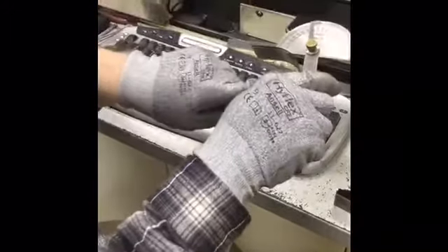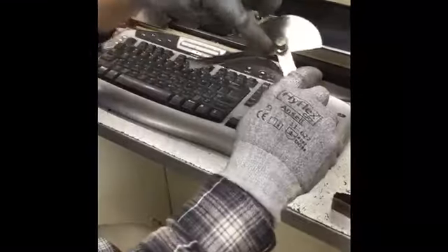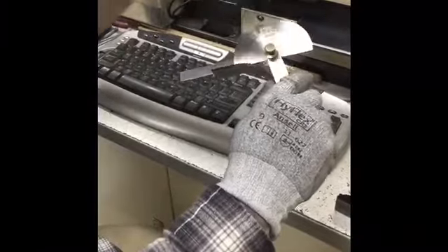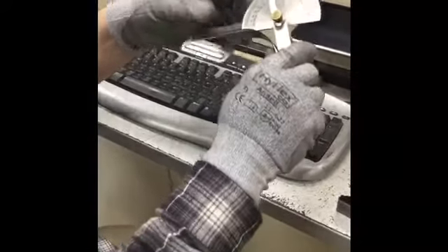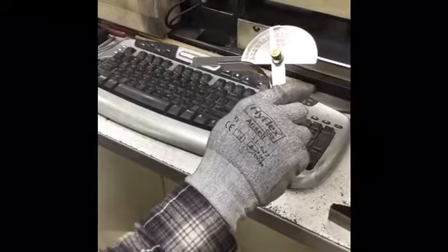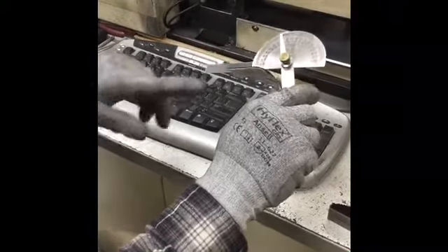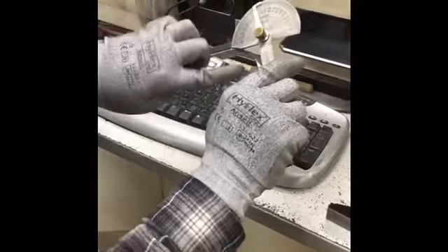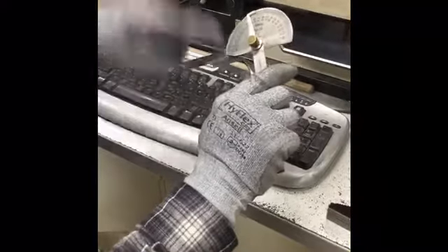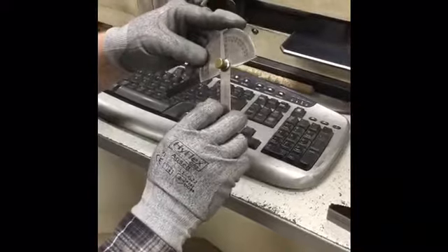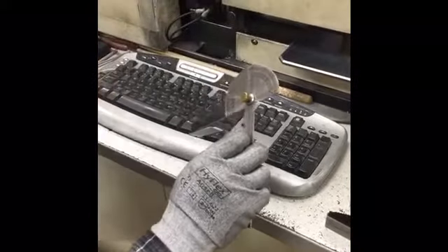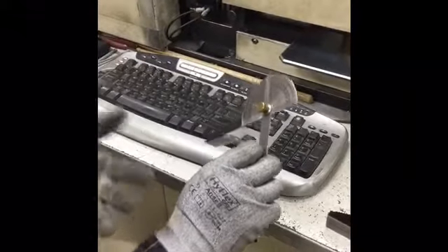You want to line that center between the 5th and the 6th bend up with where these two lines intersect on your protractor to get an accurate reading. Because it's a 10-degree bend, which again is very small, it gives you 10 hits. This is supposed to be 10. If this was exactly 10, it should all be all the way here at 100, because you divide that by 10 and get 10 degrees.